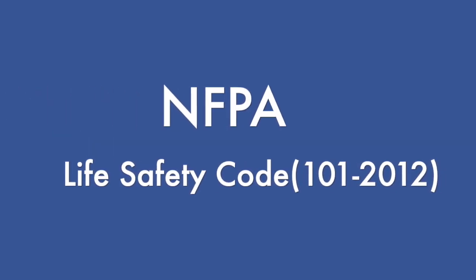Standard LS 03.01.40. The hospital provides and maintains special features to protect individuals from the hazard of fire and smoke. This will include windowless buildings or portions of windowless buildings. High-rise buildings must have an approved automatic sprinkler system. The automatic sprinkler system must meet the requirements of NFPA. And the hospital must meet all other requirements of the Life Safety Code.